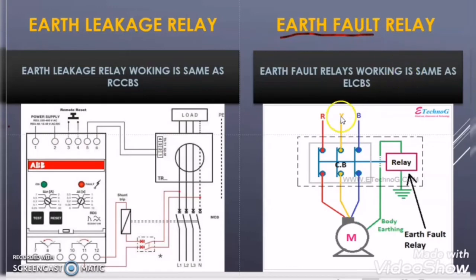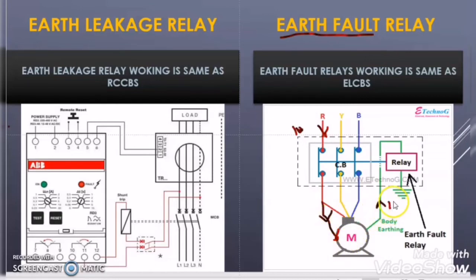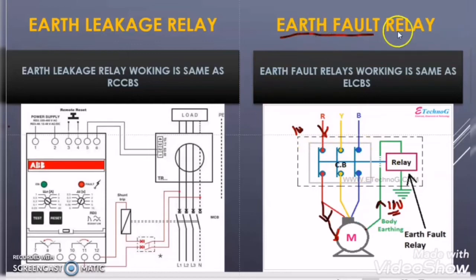For the earth fault relay: suppose the R phase completely detaches from the motor terminal and touches the motor body. Then 100 amperes of current that was flowing through R phase will now flow through the body of the motor. That 100 amperes flows through the earthing conductor connected to the motor body, then through the relay connected in series with the earth conductor. As the relay detects the high amount of current, it trips the circuit breaker to interrupt the power supply.